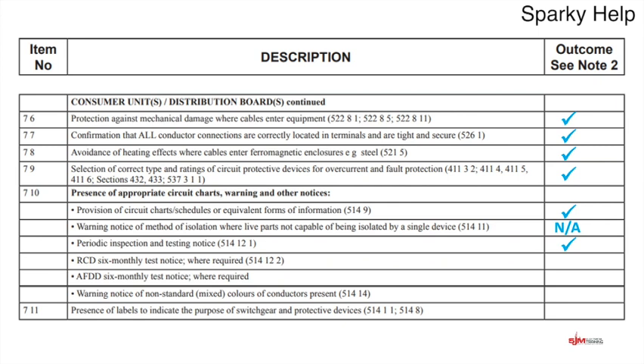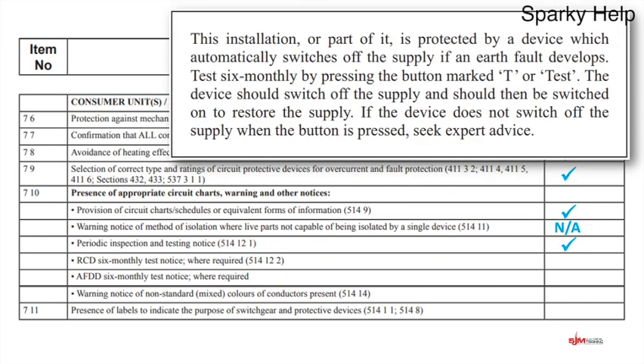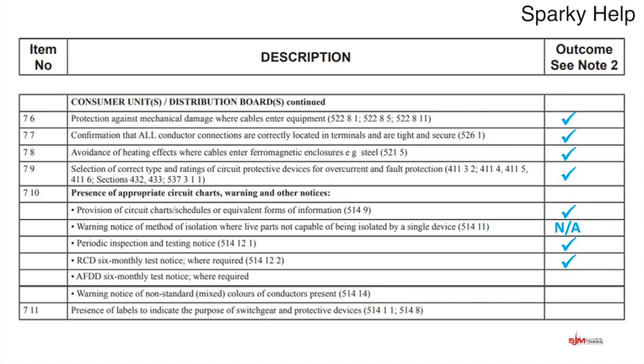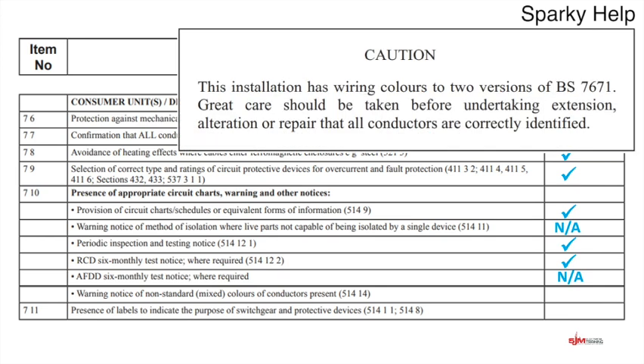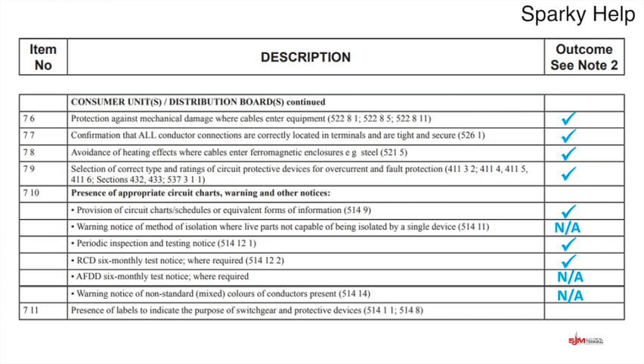So if you've got an RCD, which you probably have, it's going to have test 6 monthly, because it's not quarterly anymore. It hasn't been for quite a while now. So you'd be putting a tick. If you've got arc fault detection, obviously it would be a tick, but if you haven't, that will be an NA. Warning notice for non-standard mixed colours or of presence of other conductors. So if you've got two versions, red and black and brown and blue within the installation, this should go at the original installation to make people aware that there are two versions within this installation. Let's assume it's relatively new and it's NA.